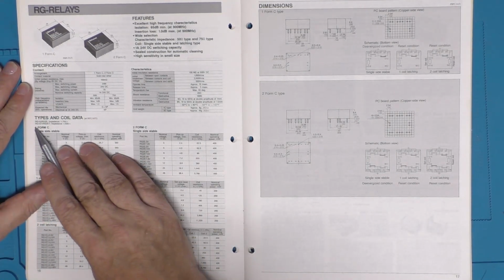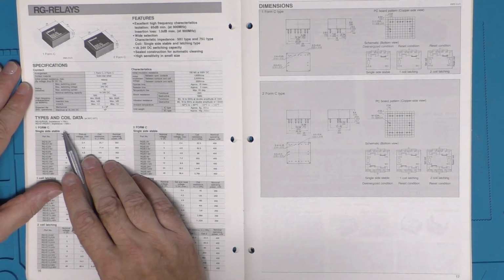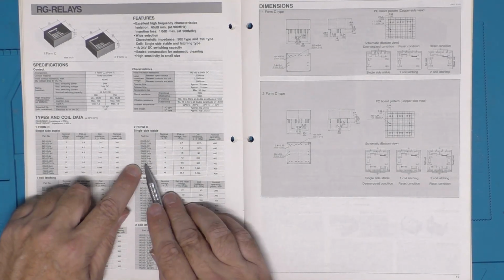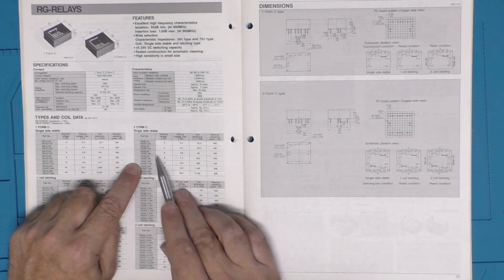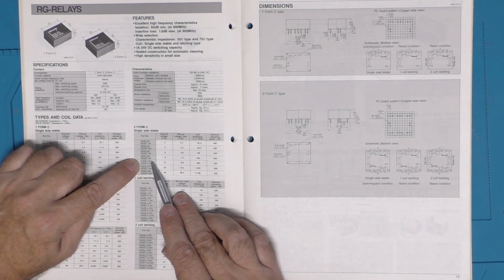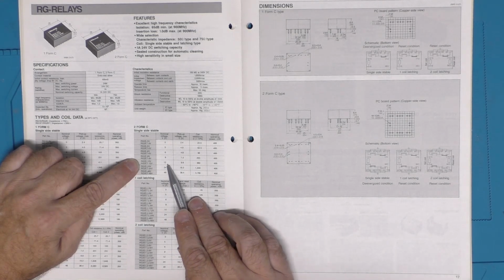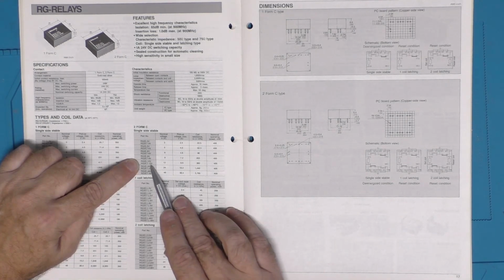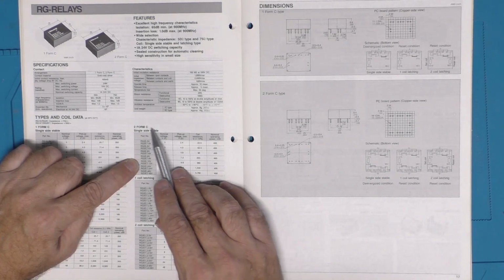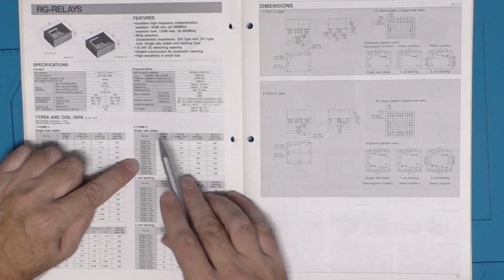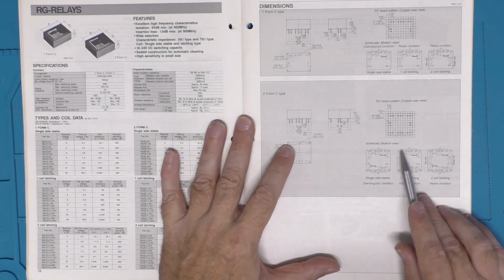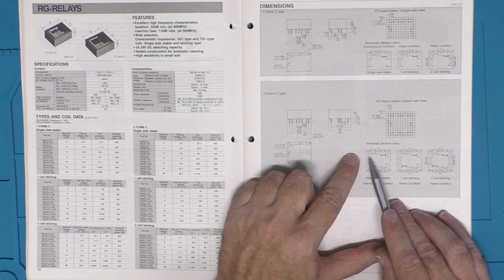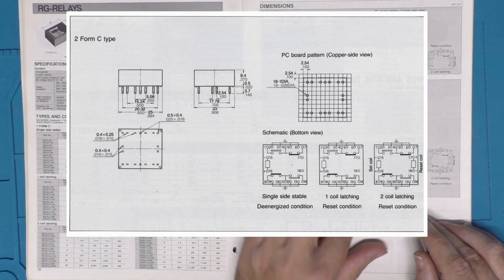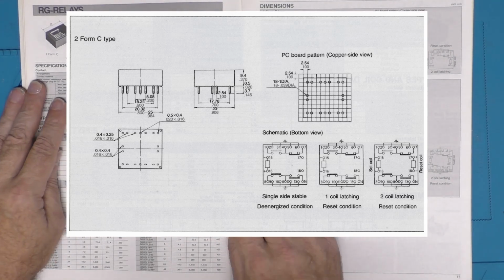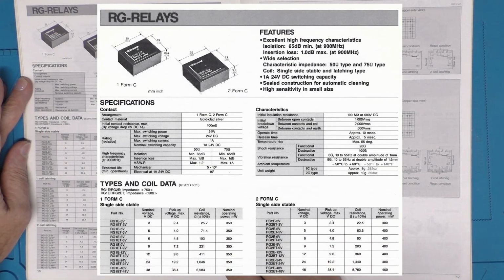The ET tells us it has a characteristic impedance of 50 ohms. The 2 tells us it's a 2-form C-type, 2 poles, 2 throws. The 12V tells us it has a 12 volt coil. It's non-latching, single-side stable. Looking at the diagram, we note pins 2, 3, 5, 6, 9, 10, 12 and 13 are connected to ground. This is normal for a high-frequency relay with a specified characteristic impedance.